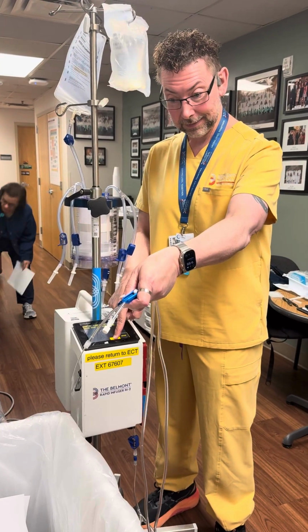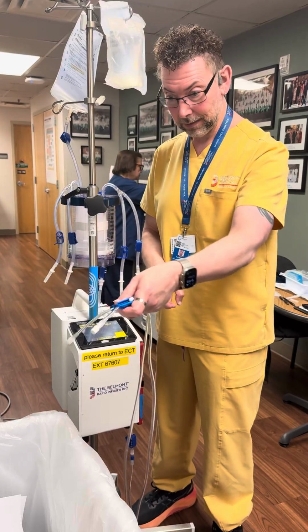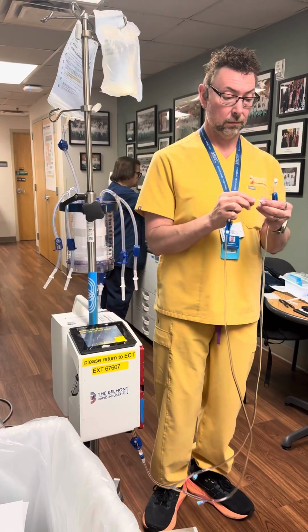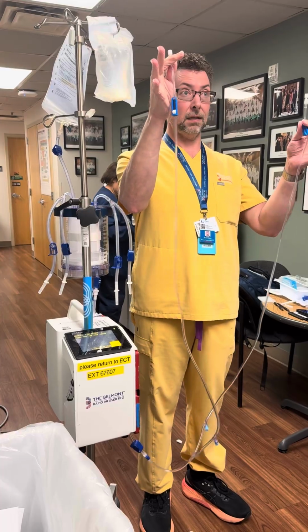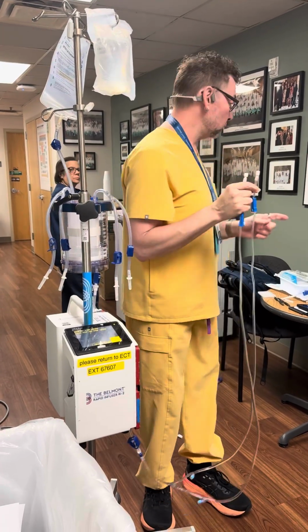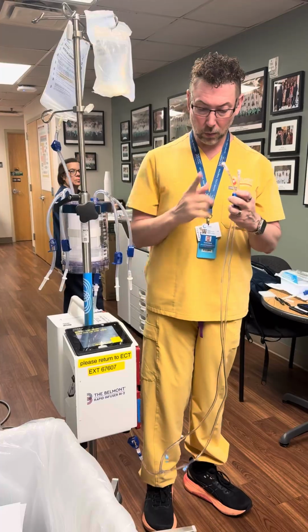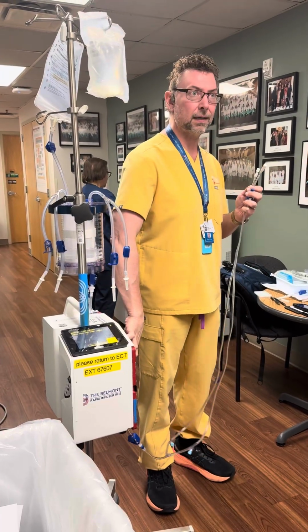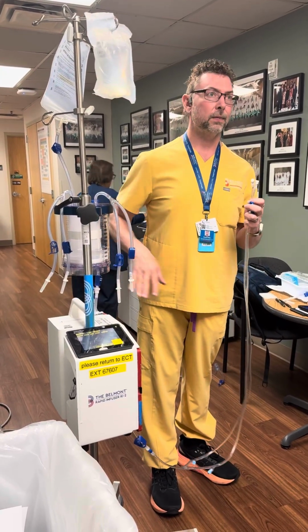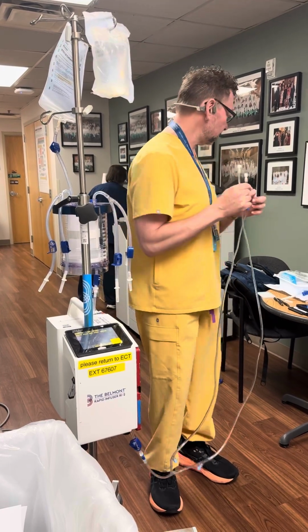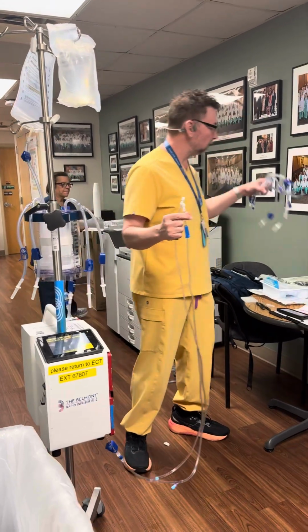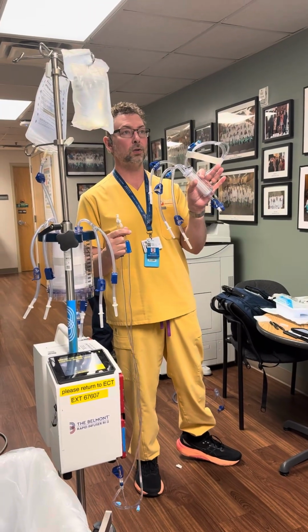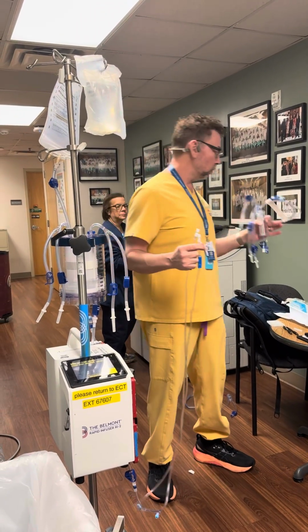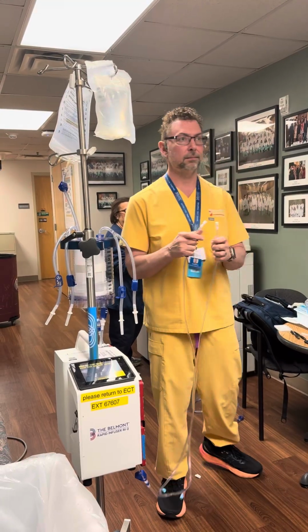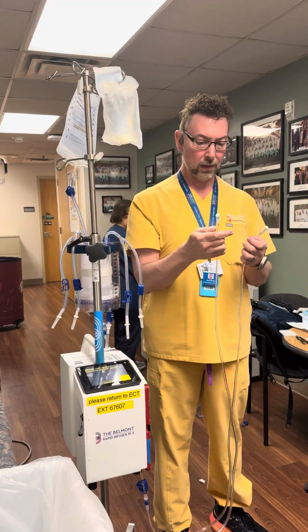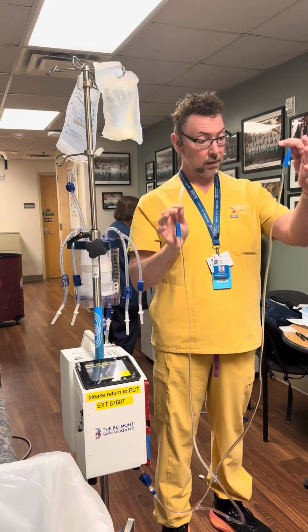What's the minimum amount of fluid in the chamber that will prime that line? 400 milliliters. It takes 400 mils to prime, because you're using the bifurcated line, 400. It seems like less than 400 in those tubes. Maybe. It's the tubes, the entire heat exchanger mechanism, plus up to here. So with the tubing set up with the single limb and the small reservoir, this is all 218 milliliters. When you throw in the large reservoir, it tends to throw in a little bit, and then the bifurcated line as well. So you would clamp off this one, load this one.